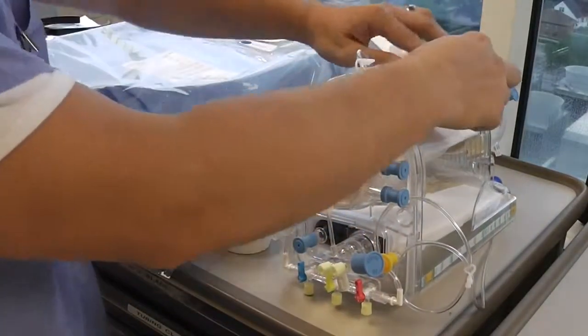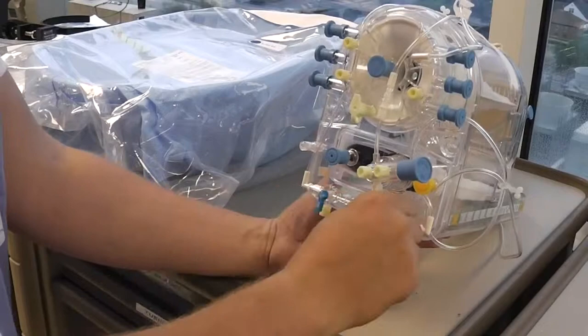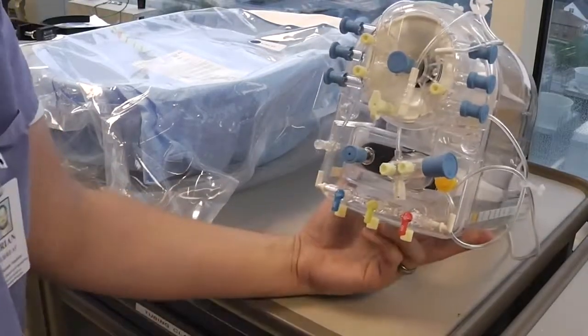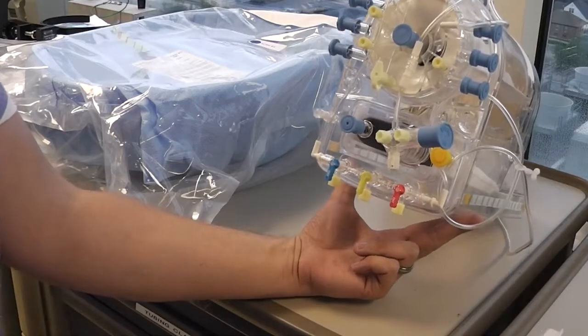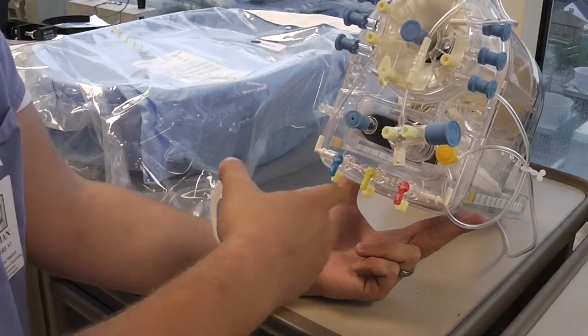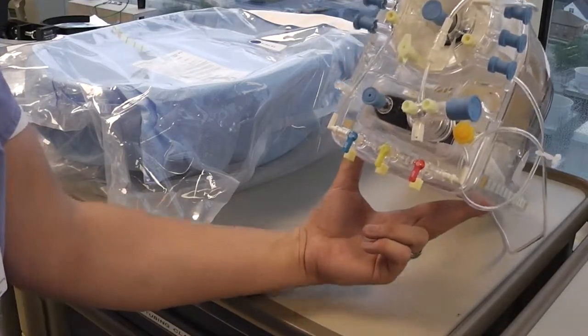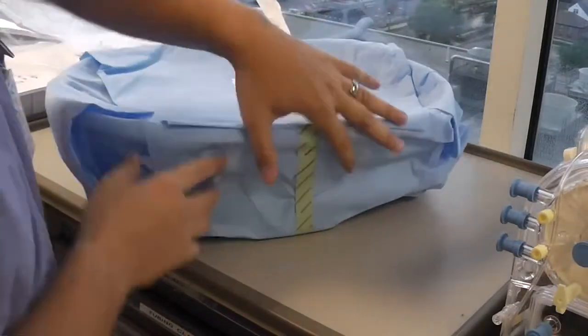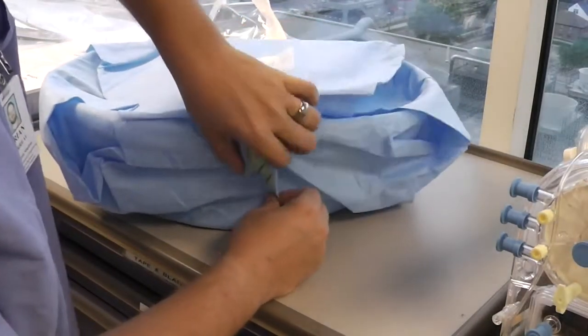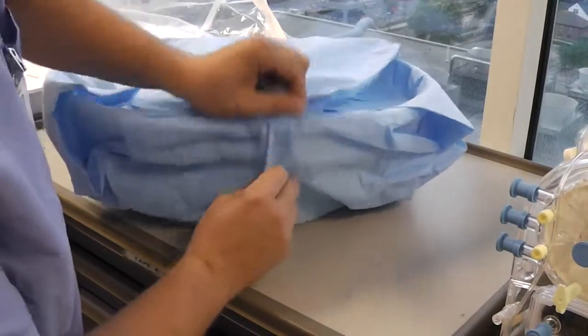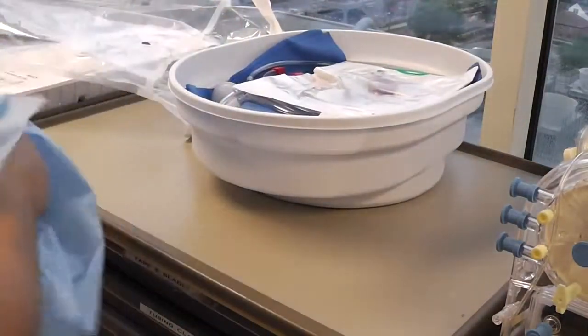Pull them off to the back of the reservoir here, and we're going to tape these lines down across the back of the reservoir. We're going to rotate these stopcocks around and make sure this manifold is seated. And if you want, it's kind of a throwback to the old one that we used to have, but I like to still put a piece of tape across this manifold just to make sure that it doesn't pop up. It's not really necessary anymore, but if you like. We're going to open up the pack. Break this green tape here. Open this up. Remove the tubing pack from the top.